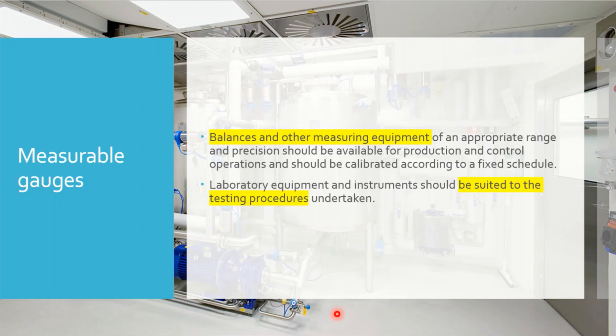Regarding measurable gauges, your process system or equipment will have a number of measuring instruments to gather process information — these can be load cells, pressure gauges, conductivity sensors, or DO probes. Balances and other measuring equipment of appropriate range and precision should be available for production and control operations, and should be calibrated according to a fixed schedule. Laboratory equipment and instruments should also be suitable for the testing procedures undertaken.